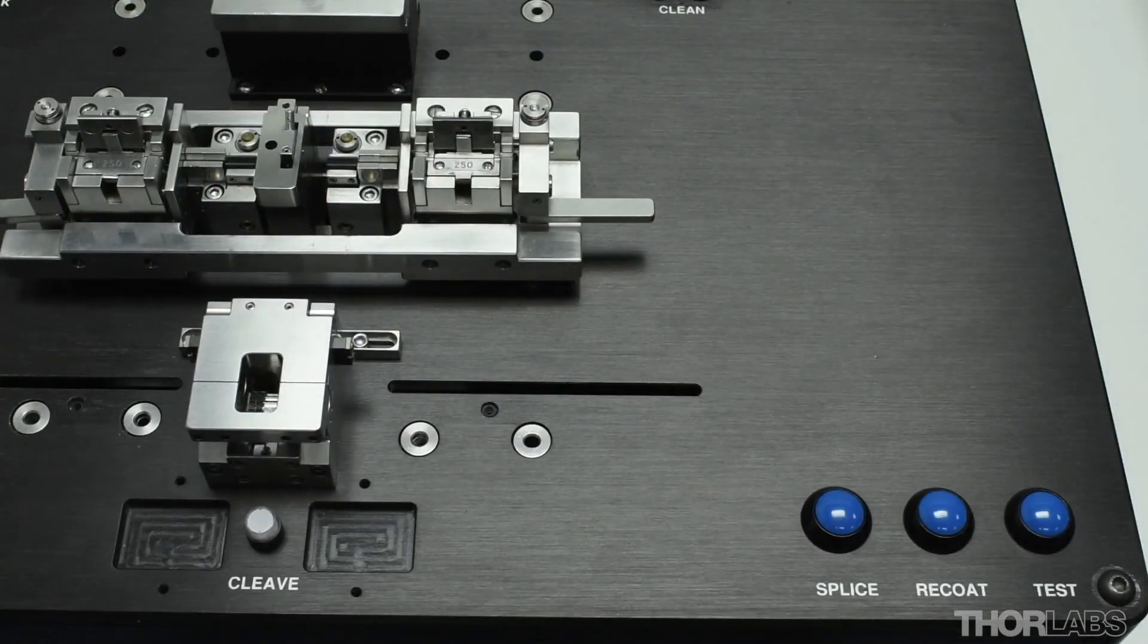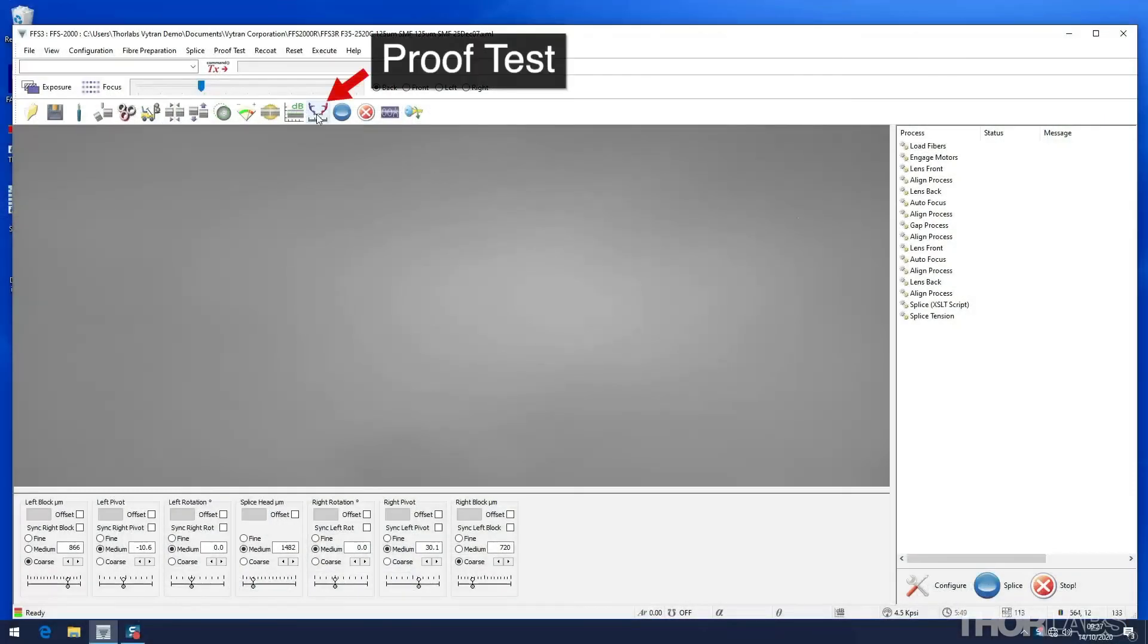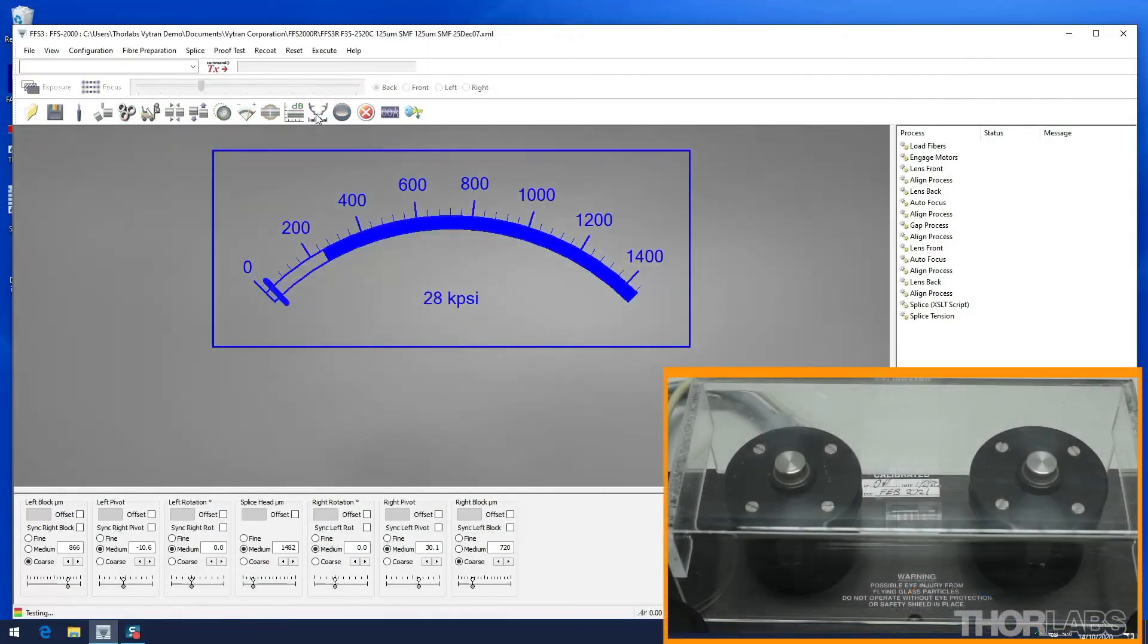To initiate a proof test, either press the test button on the unit or click the proof test icon in the software. The right hand mandrel starts to rotate and the proof tester's strain gauge monitors the force applied to the fibre and reports this to the software.